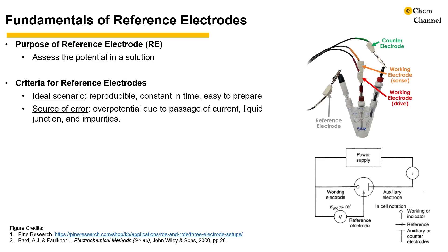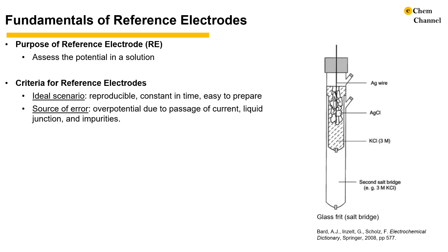There are several intrinsic sources of errors associated with the reference electrode. Ideally, the reference electrode is non-polarizable; however, in reality, a small passage of current will cause an irreversible reaction at the reference electrode and move the potential away from equilibrium. The second source of error could be the liquid junction across the salt bridge between the reference electrode filling solution and the electrolyte — it is usually negligible, but the error will increase in dilute solutions. Lastly, impurities can change the electrode activity, react with the electrolyte, or react with the electrode, changing the equilibrium potential.